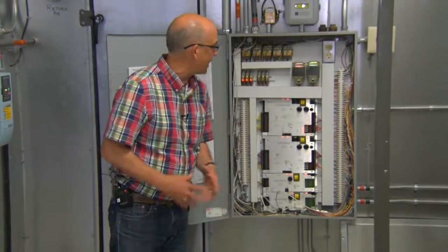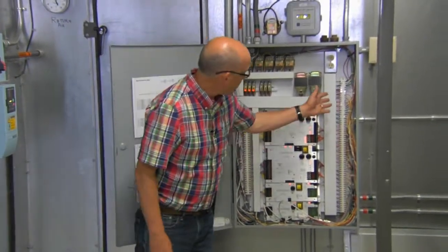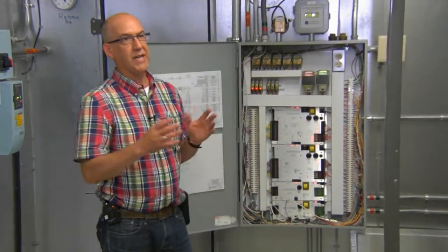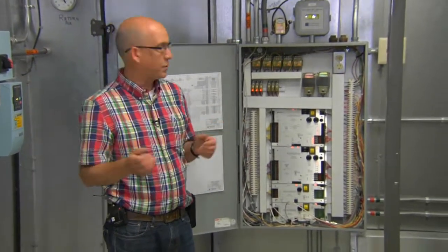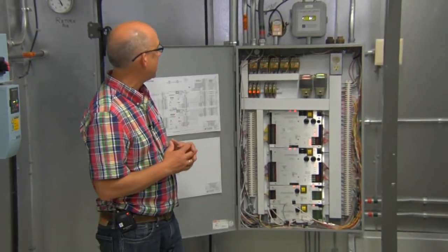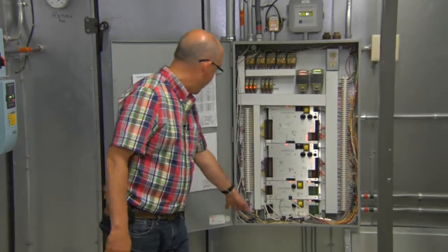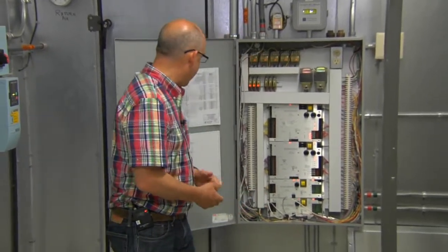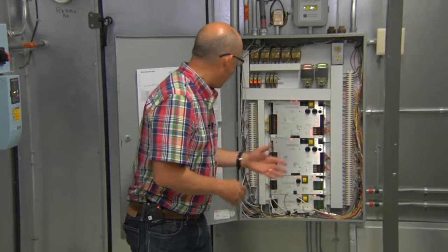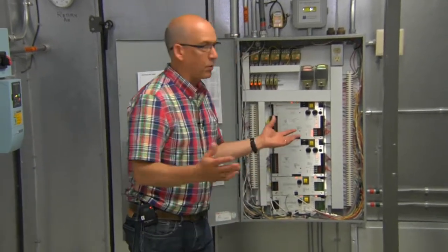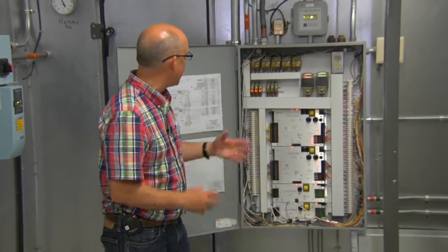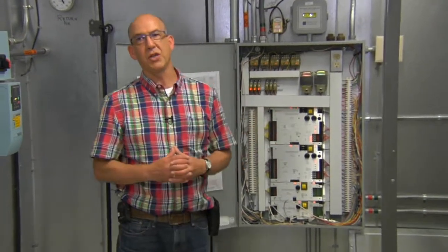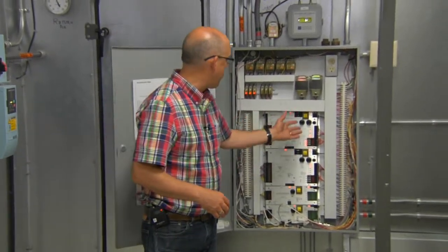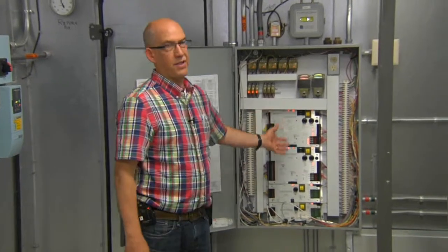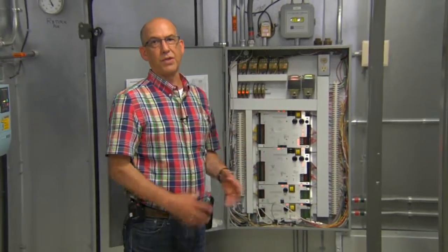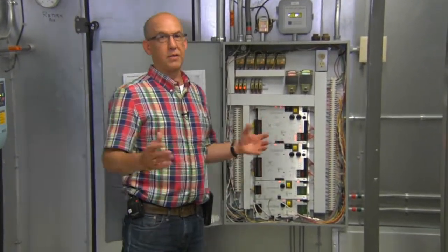Over here on the right, we can see the terminal strip. And we just want to spot check and make sure that we don't see any signs of wires that have been removed or loose, any jumpers in place, anything like that. So everything looks pretty good. And I would say that, again, if the people who are taking care of the controls are on top of things, they're probably aware of any communication issues, whether or not there's any failures in the hardware. This is the heart of the control system for the rooftop unit or units.